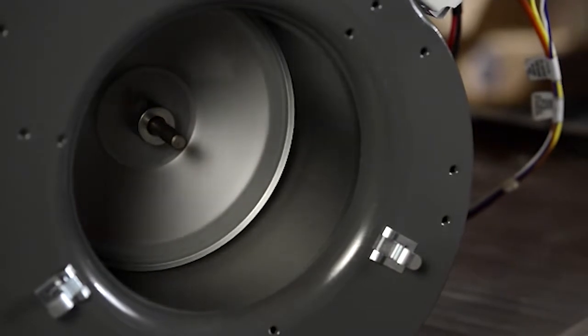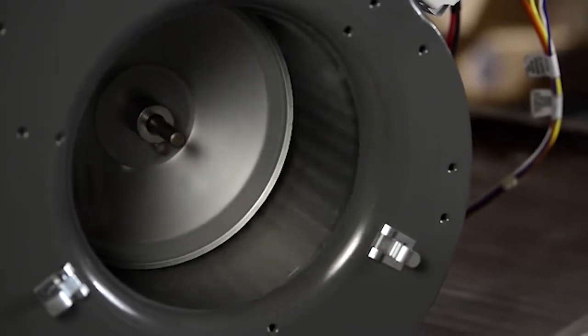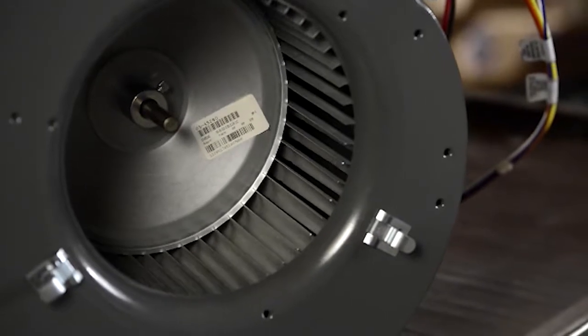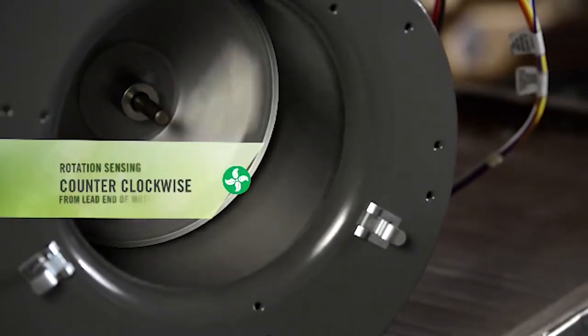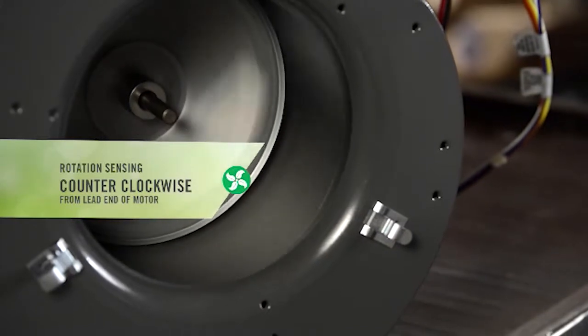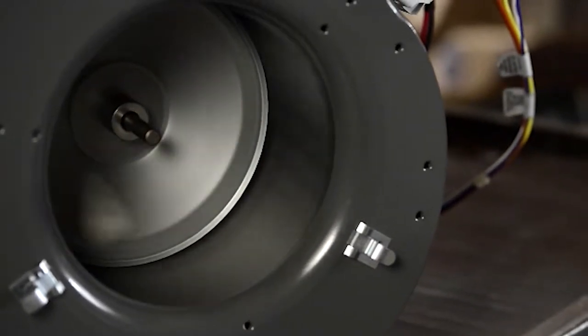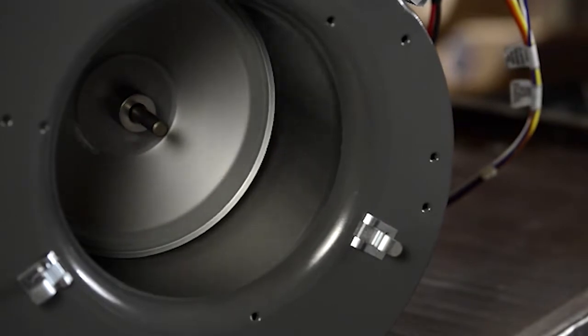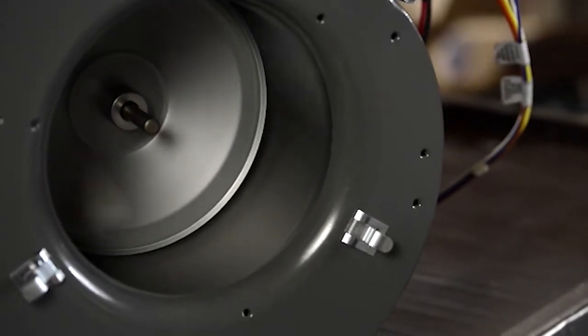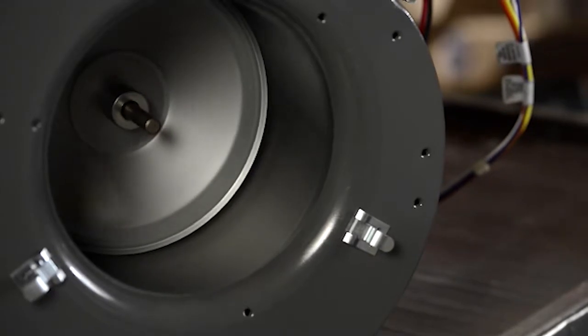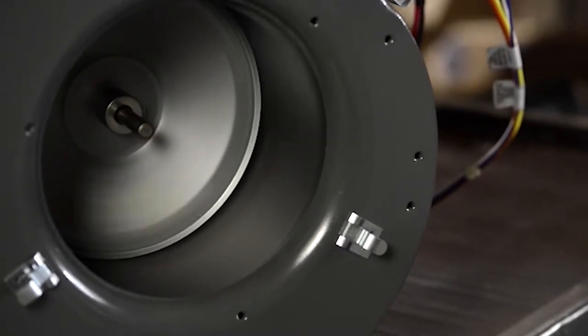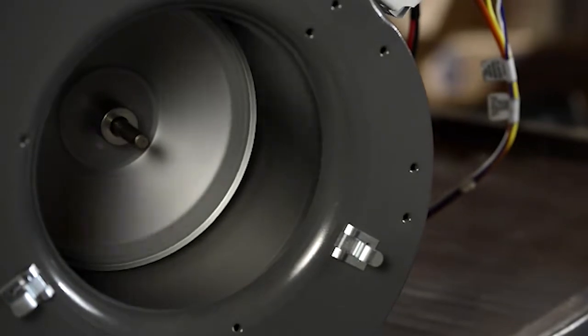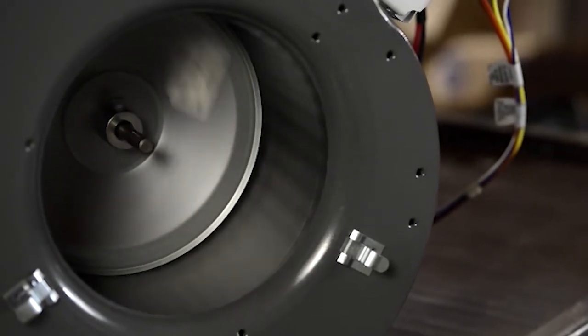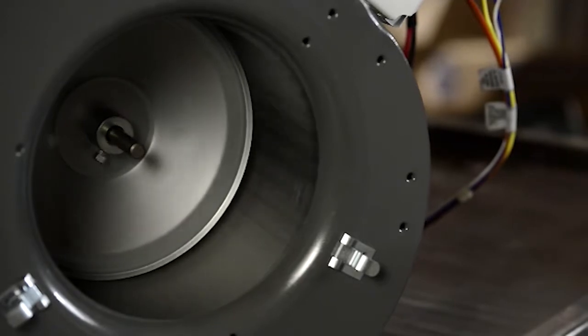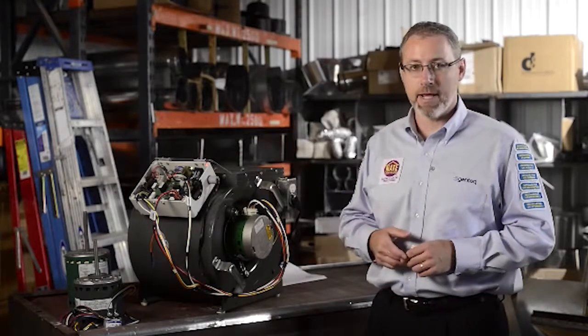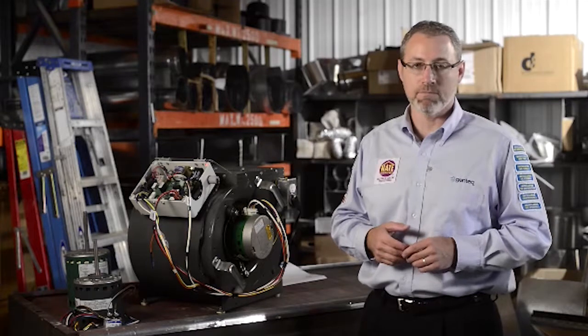Then it's going to do something that's going to weird you out. It's going to shut off. It's shutting off so that it can reverse and run the opposite direction for another 10 to 15 seconds at that very low RPM. What the microprocessor is doing is running the wheel at the same RPMs in both directions, measuring the current or the power, and determining which direction takes the most power to run the blower wheel. So if the motor actually needs to run clockwise, it's going to stop one more time and then turn on to the counterclockwise direction, running at whatever demand you've got turned on in the HVAC system.